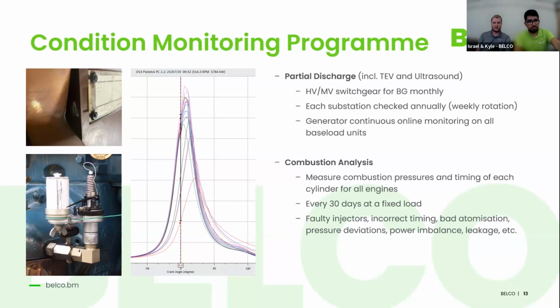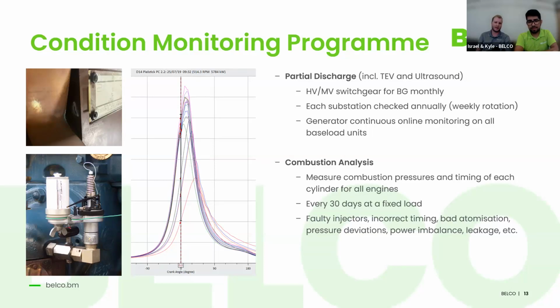As well as that, we do combustion analysis on each of the reciprocating engines. We measure each cylinder's combustion pressure and timing, and it overlays them into a nice graph. We do this every 30 days at a fixed load, and we look for things such as faulty injectors, incorrect timings, bad atomization, pressure deviations, power balance, leakage, and a lot more that it can tell us.